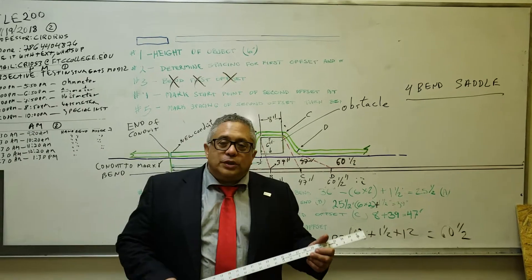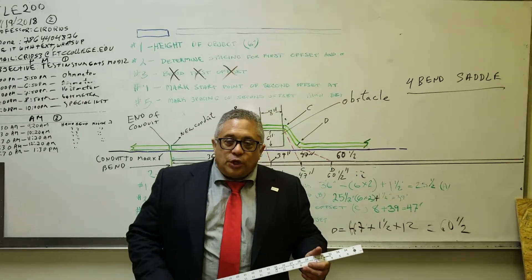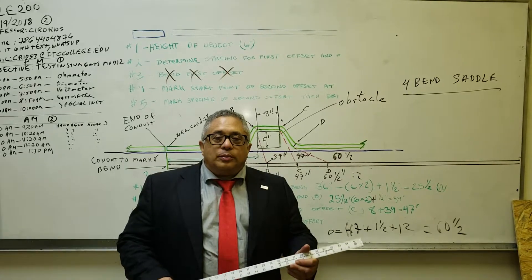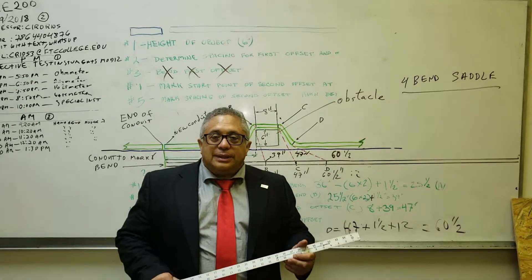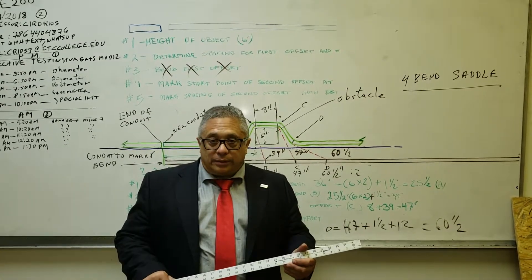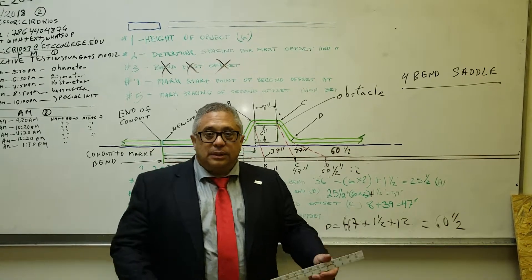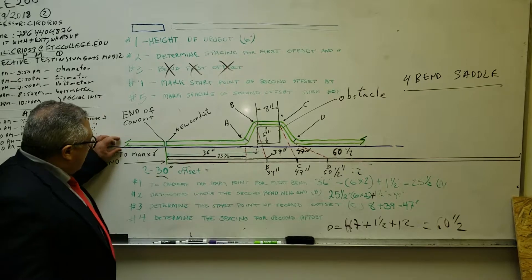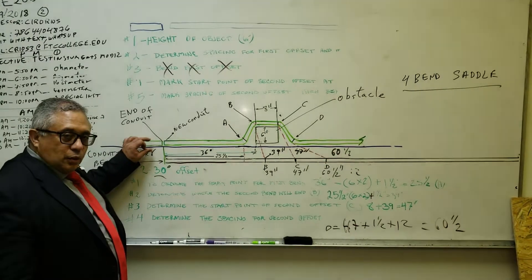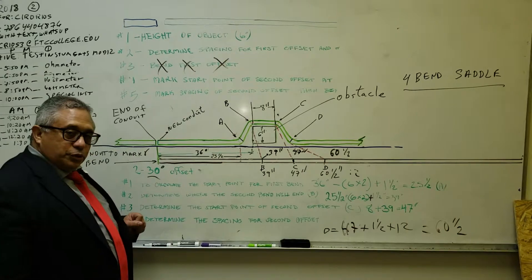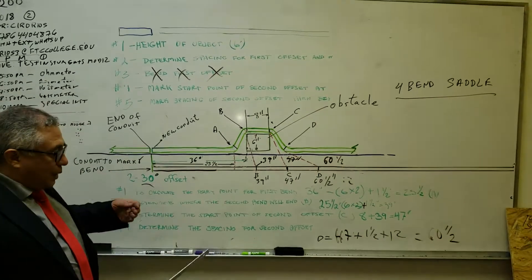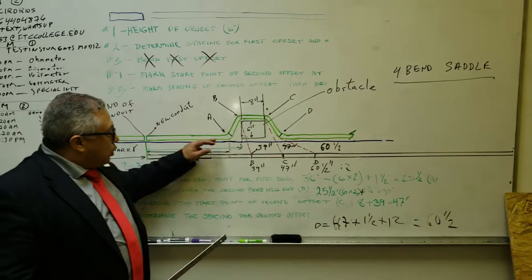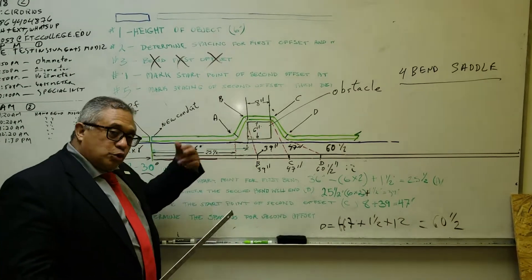When you will be using a four-bend saddle, you will use it when you want to overcome an obstacle that is square or rectangular. What is the occasion? You are lying down your conduit, and you end in a certain position. When you get a new conduit to continue lying down, you realize that you have an obstacle to overcome.